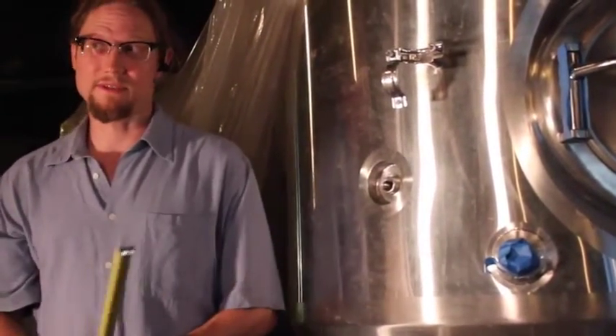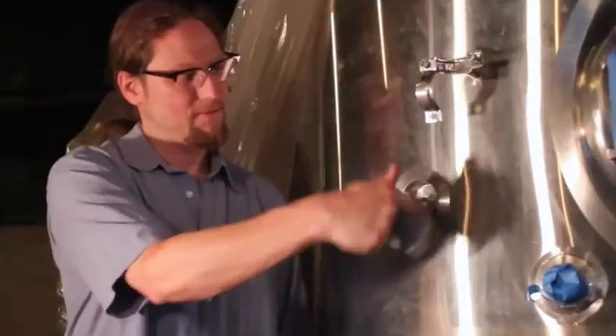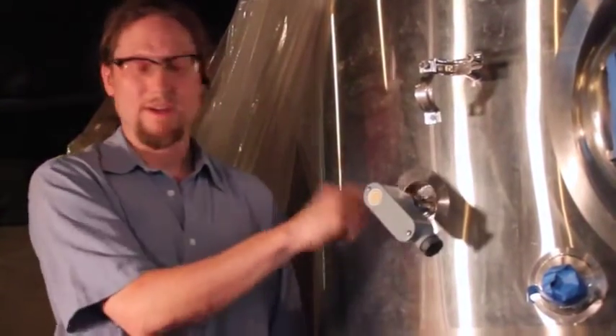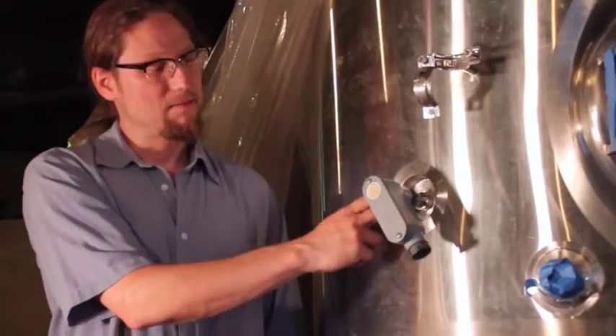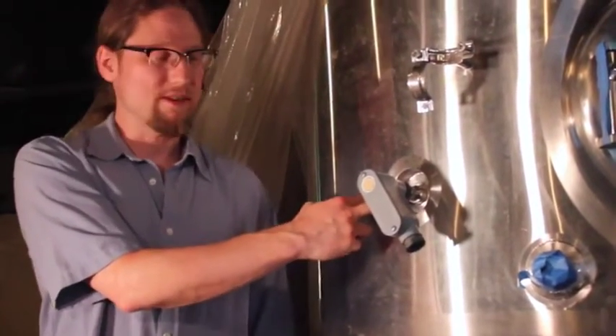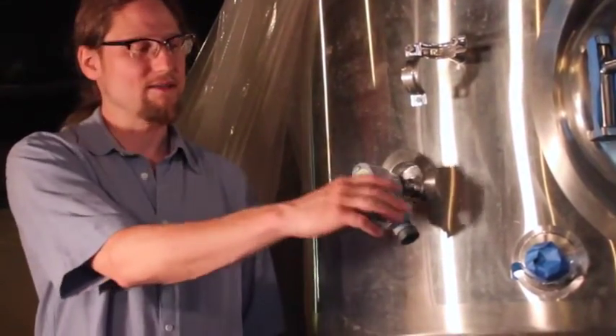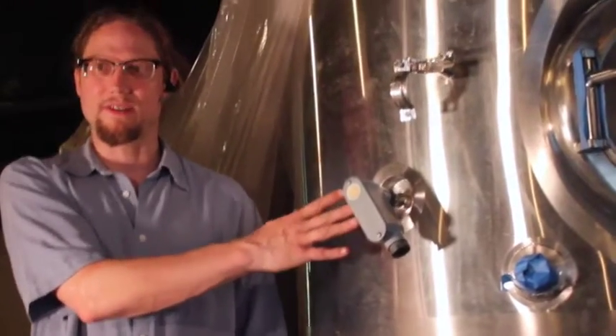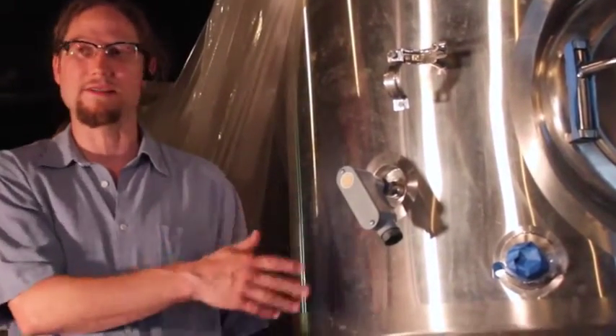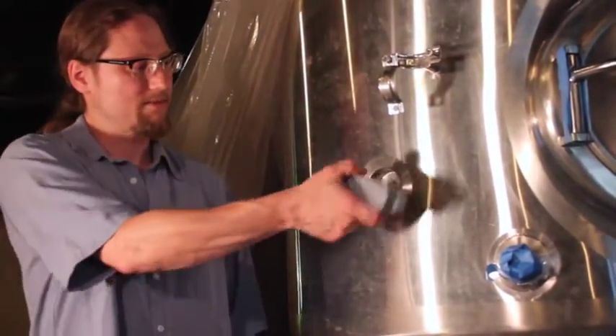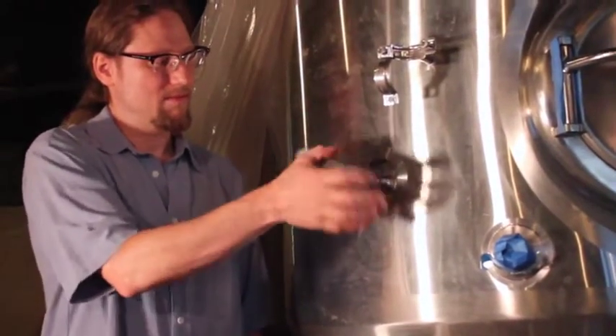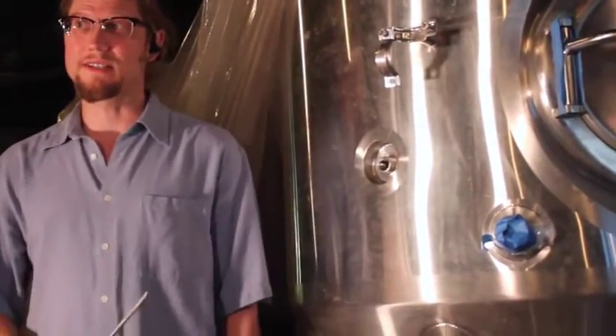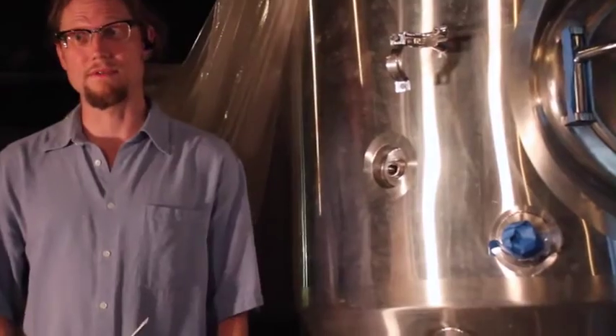So let's see what happens when we try to use a 9-inch probe. The threads lock up, but the temperature probe never hits the bottom of the thermowell. So by using a 9-inch probe, you think it's working, but in reality it's not bottomed out and it won't get an accurate temperature. So the solution in this case is to use a 9.5-inch probe.